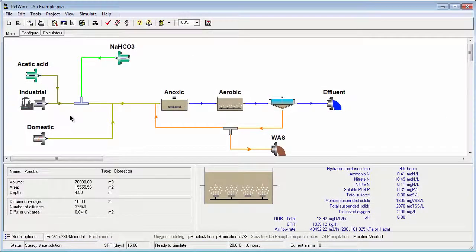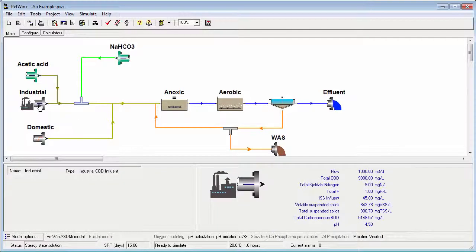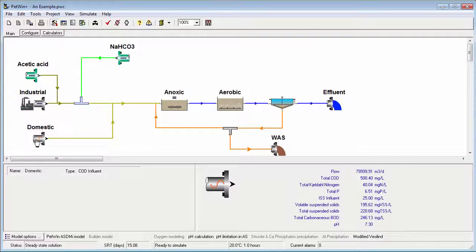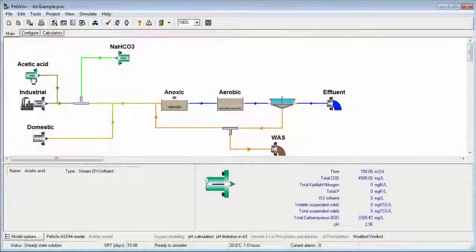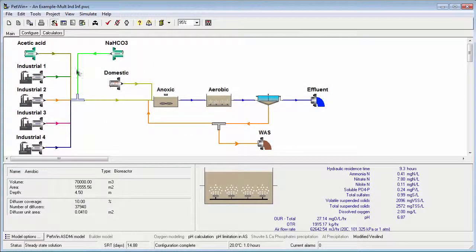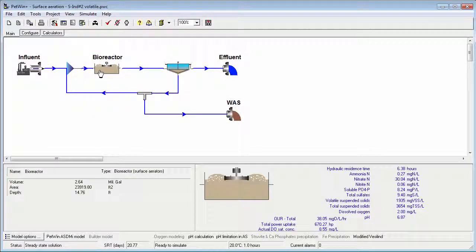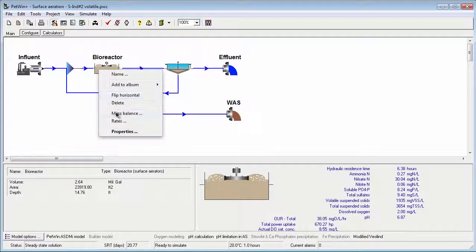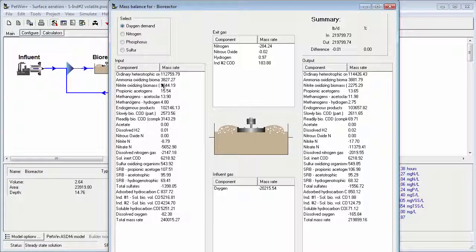Industrial wastewater treatment will have added complexity compared to municipal systems. For example, there may be a mix of industrial and domestic influent, and each of these may have very different composition. An industrial treatment process may also have requirements for alkalinity and nutrient dosing. Industrial wastewater treatment processes often have multiple industry-specific influent streams with different compositions. It could be necessary to account for stripping processes in addition to biological degradation of certain organic compounds.